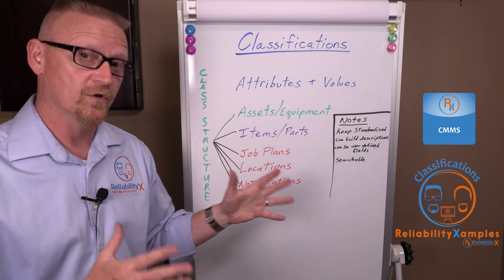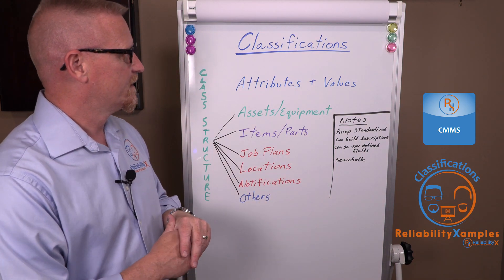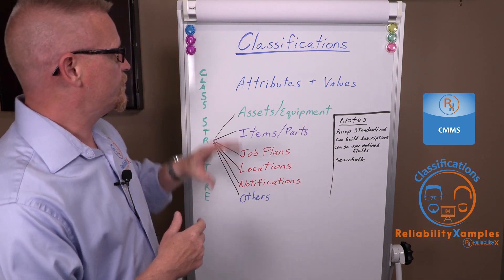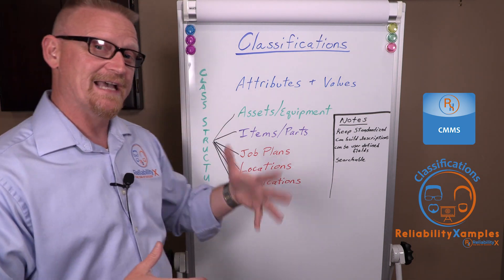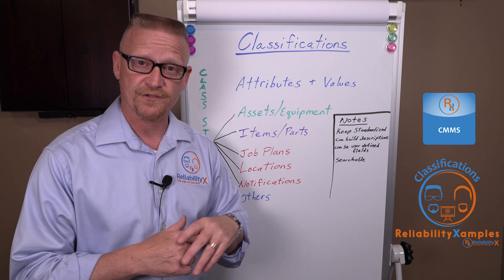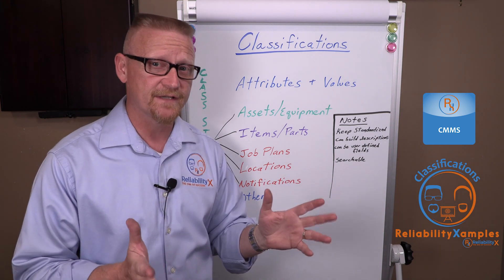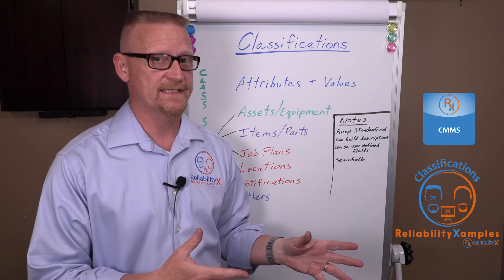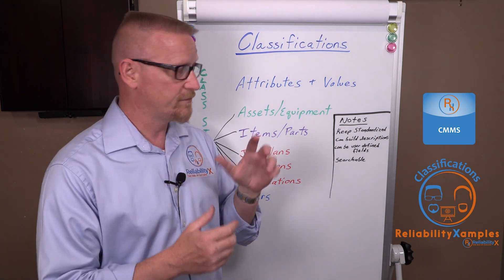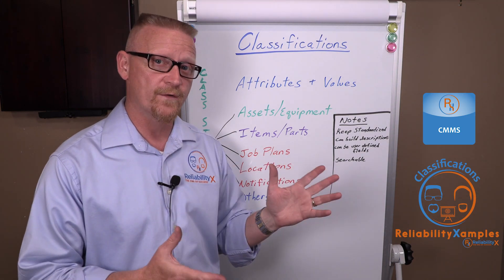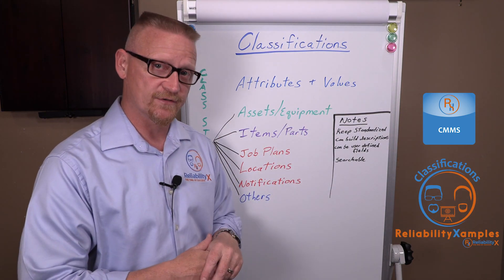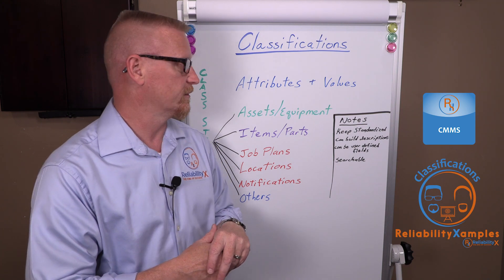A couple of things to remember: when you create your classification database, that should be standardized. There shouldn't be 50 different ways to say that this is an AC motor. When you build your class structure, have one way to say it's an AC induction motor and apply it to all your AC motors.